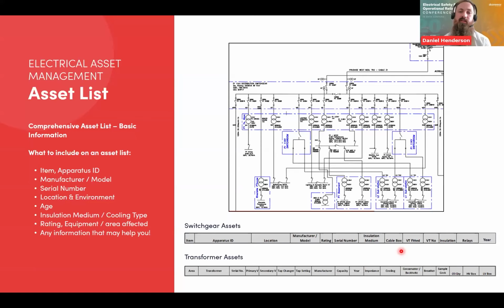For those of us who manage electrical networks, anything that's going to help, include it in your asset list. Does it have a voltage transformer fitted? If it does, what's the insulation medium? What's the serial number? Again, we need to know where VTs are from a risk perspective as well. Relays: it's quite a small box on here, but you might need a comprehensive list of what protection relays are fitted, and probably a separate document that has what relays are fitted and what settings they have. That's all quite important from a maintenance perspective. And then year of manufacture is also good to include, if you're going to start looking at age, which we'll look at further down the line.